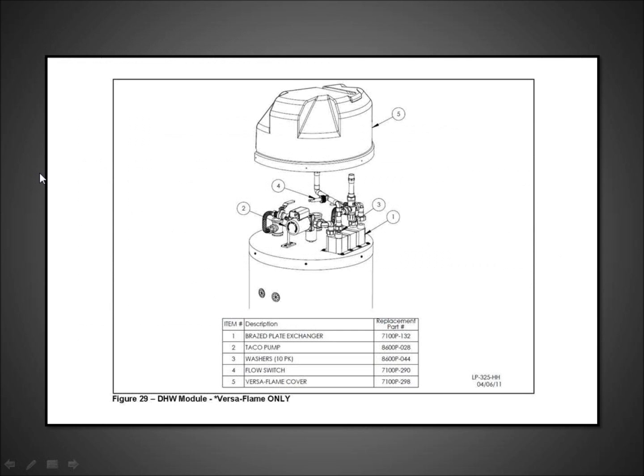Just to look at the device, we have this nice little shroud that gives it a nice aesthetic look. Here's our braze plate. On the domestic side, everything's already pre-piped. This is the hot water mixed outlet. We have our cold feed here with the flow switch, which is number 4. So that's the domestic side, which is on this side and this side. And then this is preset, this mixing valve, which is a TACO mixing valve, and it's ANSI rated 10, ASSE rated at 1017. That is preset to 119.